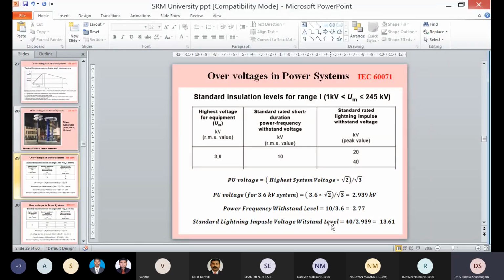Standard lightning impulse withstand level is equal to, you can see here they have given two values, 20 and 40. Why they have given two values: the values 20 and 40 depend upon the ground impedance value or earth impedance value. If the earth resistance is very low, the preferred range is 5 ohm to 12 ohm, then we prefer to have 20. If not, we have to consider a standard lightning impulse voltage of 40.